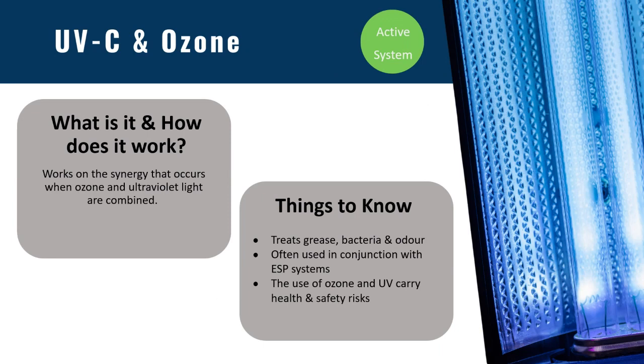UVC and ozone. A few companies have combined ozone technology and UVC to try and address odour and grease. How does it work? It works through the synergy that occurs when ozone and ultraviolet light are combined. UVC stands for ultraviolet light in the C-band, a very strong type of ultraviolet light. Using light energy on grease particles disrupts them, and they are oxidised in the ductwork with ozone, which causes contaminants in the air to be destroyed. This results in the reduction of odour emissions to the surroundings, as well as reduced grease deposits in the ductwork.